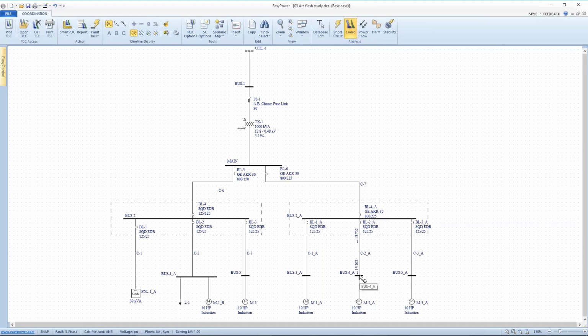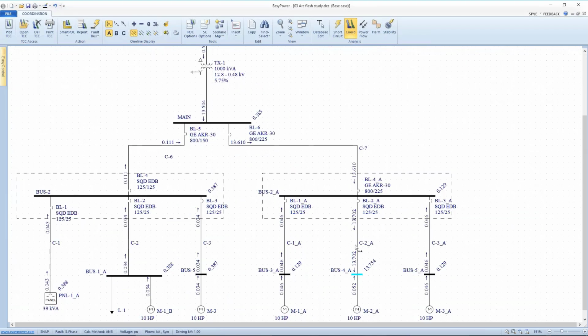Series coordination, by definition, means I want this protective device to eliminate the fault as soon as possible. I want this protective device to be slower so that it gives the downstream breaker a chance to work, this to be slower still, and then finally the fuse to be the slowest of all, so that I don't take down the whole plant for just this remote fault. Well, EasyPower makes available this coordination module, which allows me to go in and fault the bus. Let's say fault this little bus down here by this motor. What it's showing me now, if I fault this single bus, is the fault current that's coming from the utility, 13702, the fault current coming from the motor.